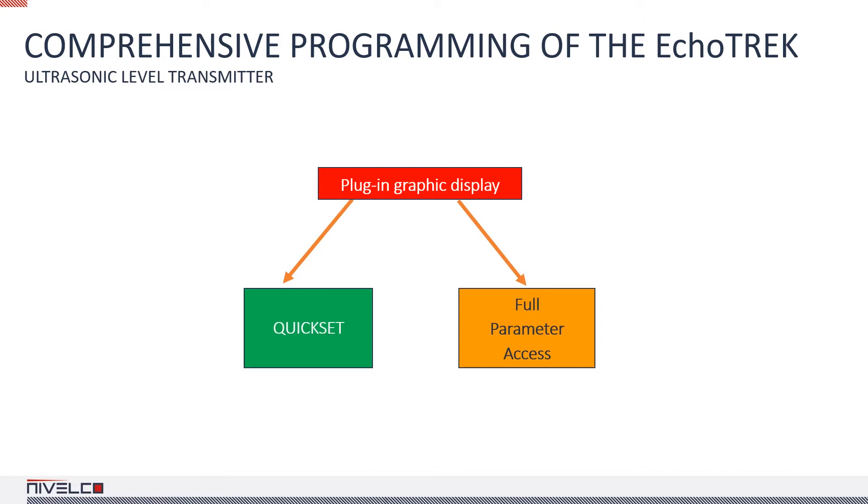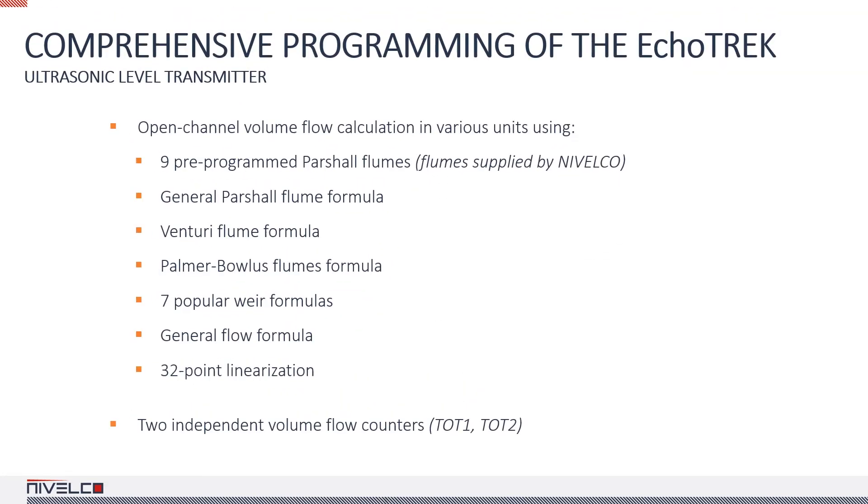If your device is HART compatible, you can use a Multicont unit or the eView configuration program on a Windows PC to modify the parameters. There are numerous calculation options in the EchoTREK for open channel metering, including 32-point linearization, 9 pre-programmed Parshall flumes, a general flow formula, and many specific formulas.